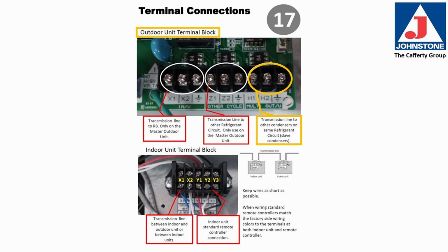Transmission line to the other condensers on the same refrigerant circuit, also known as the slave condensers, H1, H2, and shield. The indoor unit terminal blocks. The transmission line between the indoor and the outdoor unit, or between indoor units, is the X1 and X2. The indoor unit standard remote controller connection is Y1, Y2, and Y3.